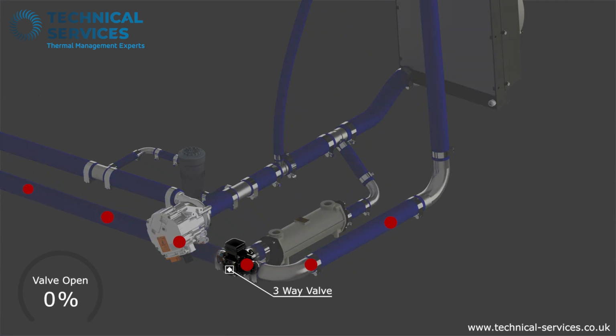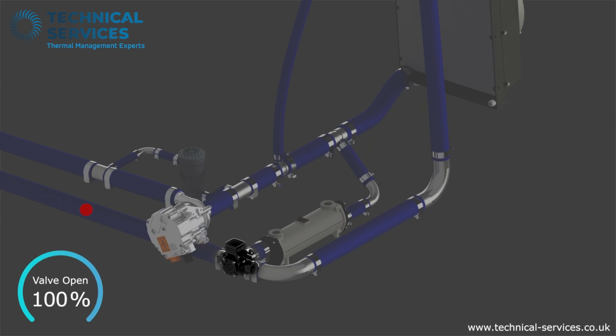The first is a high flow rate three-way proportional valve, designed for mixing and diverting coolant that has a high flow rate while maintaining a low coolant pressure drop. When used at either of its extremes, the valve will send 100% of the flow to either the heat exchanger or the bypass. Within the fuel cell's own balance of plant, three-way valves will often be used to maintain a precise inlet temperature to the stack, protecting the fuel cell membrane and shortening warm-up time.